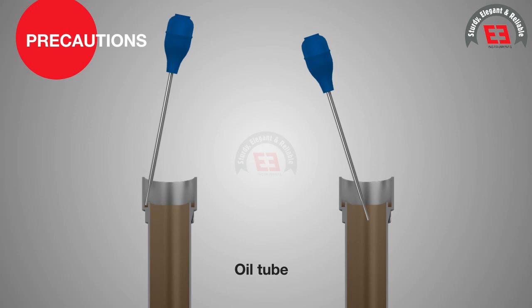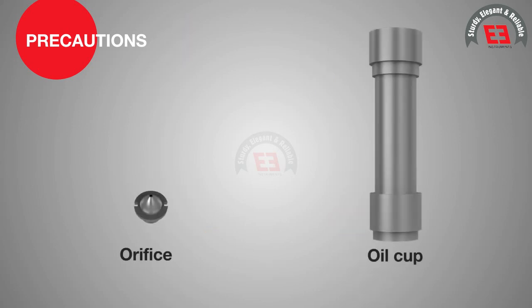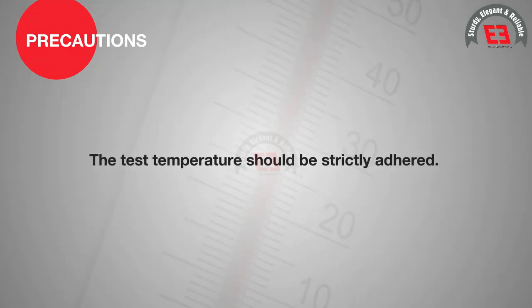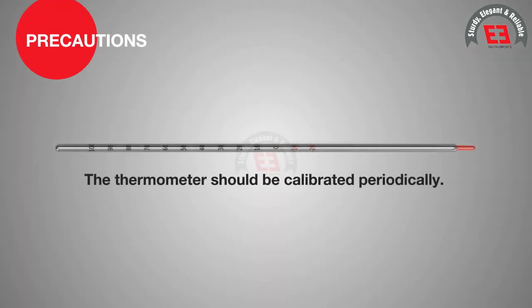Precautions: The test shall be started over again if the tip of the withdrawal tube touches the overflow rim. The oil cup and orifice should be thoroughly cleaned. The test temperature should be strictly adhered to. The thermometer should be calibrated periodically.